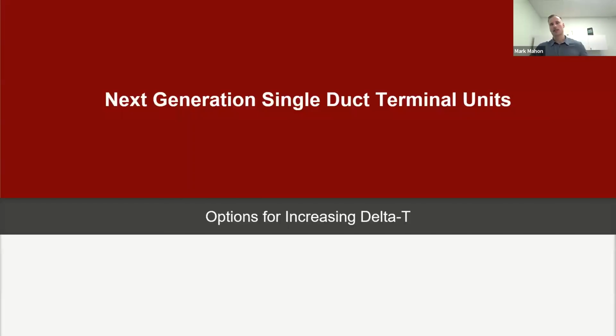Strong agreement from me. I actually think 85 from an ASHRAE perspective is maybe a little generous to the design engineer. And really, we'd like even lower than that in some cases. But let's leverage what ASHRAE 62.1 and 90.1 indicate to us. I personally would, if I was the engineer of record, be assuming a max of 85 for leaving air temperature, just to really help with the mixing and the air distribution side.